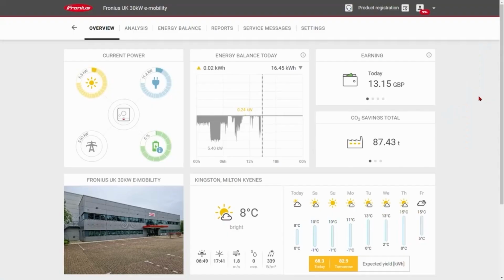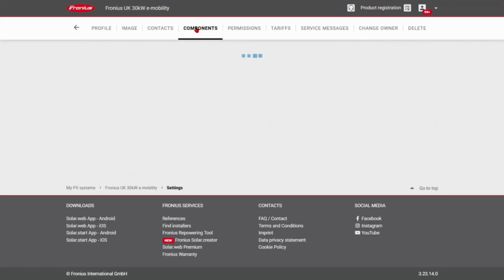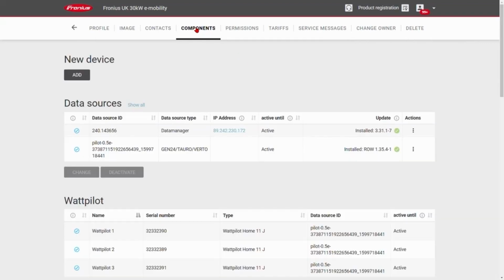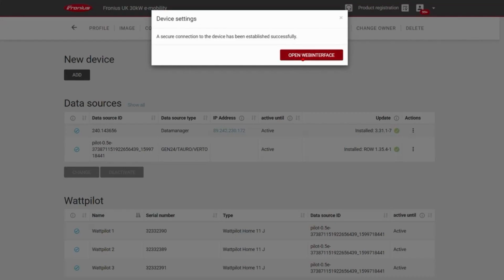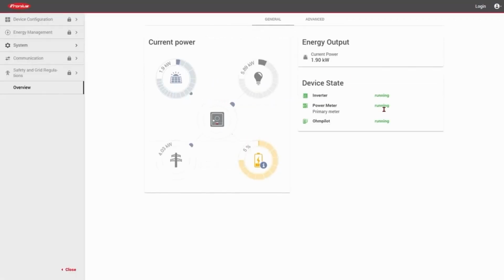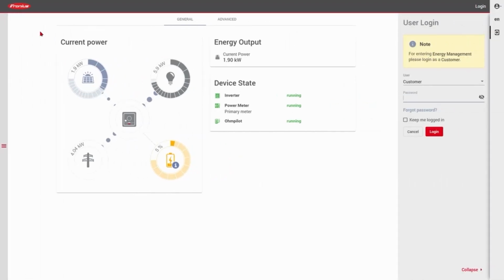If you want to make more complex changes to your system, we'd recommend using the Fronius Solar.web remote access. This can be done from anywhere in the world, provided you're connected to the Fronius Solar.web browser version. Go to Settings, then go to Components, and you shall see the inverters listed. On the right hand side there is a small button under Actions. Click on this and you can then connect to the device settings. After a few seconds, the device will attempt to open a connection to the inverter and you will then have access to your device. From here you can make changes to the battery time of use charging, maybe add a reserve capacity to the battery or change any other settings within the device.